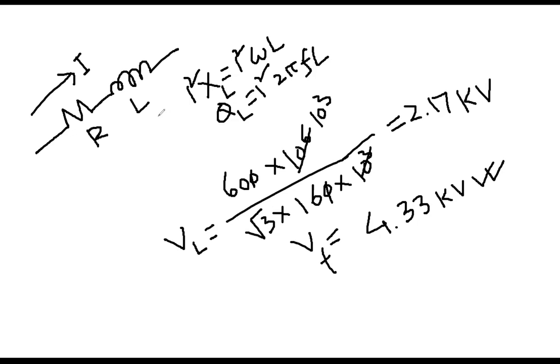There will be some power factor issue as well. Power factor will be low lagging because of this. That's why you have to take care of reactive power as well. So the appropriate answer is you have to control both active power and reactive power. Active power control means frequency, that's fine, but if you analyze the inherent situation, the mathematics tells you it is related to frequency through reactive power consumption. Because there will be huge reactive power loss, you have to handle reactive power as well, so both controls are needed.